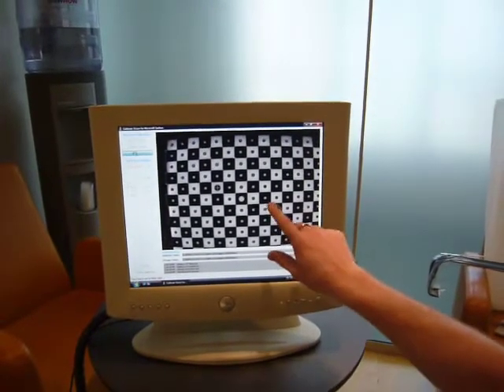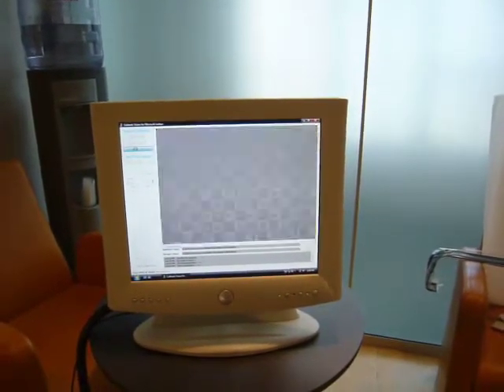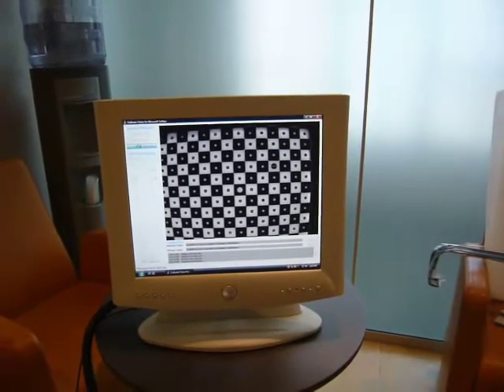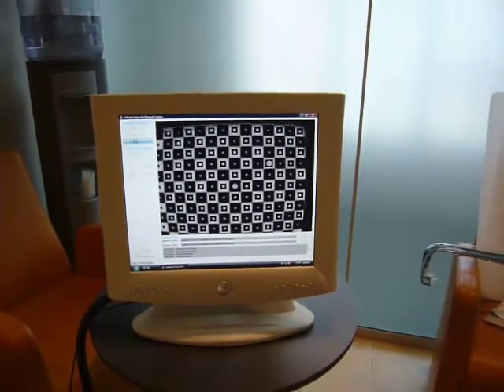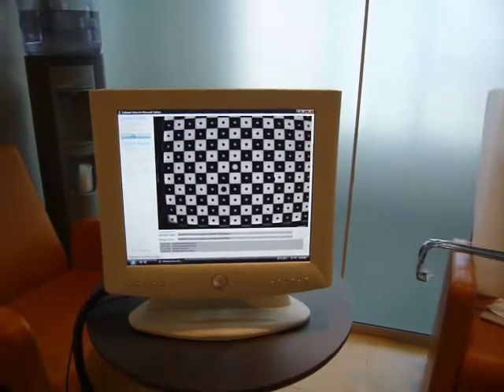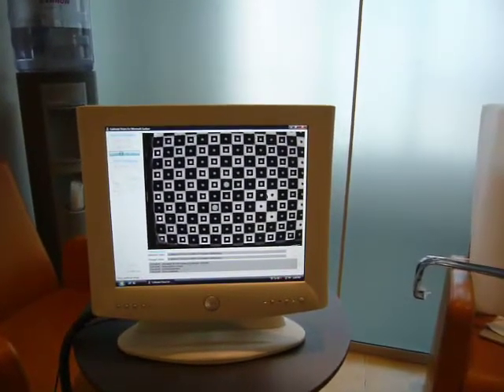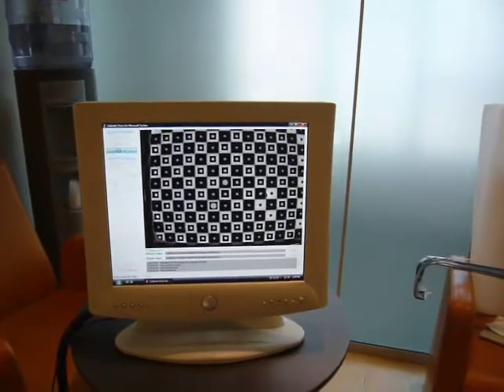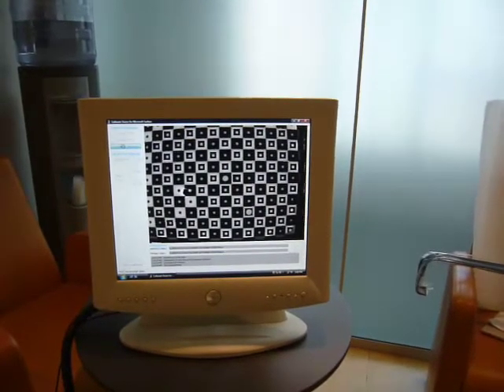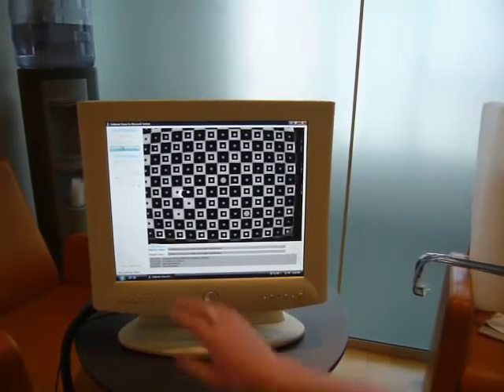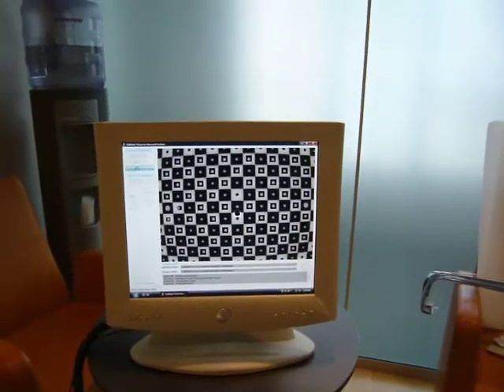You will see here that it will start working through the dots on the calibration board in line with the actual cameras inside the device. It's lining up, and it will go through this for all the different cameras. Finally we are on camera 5.